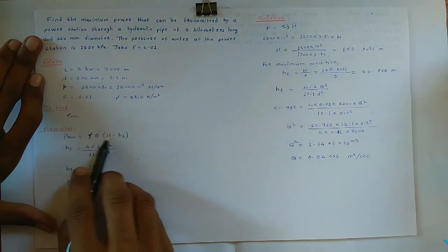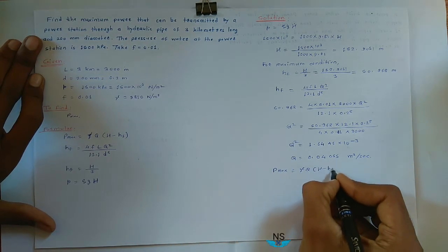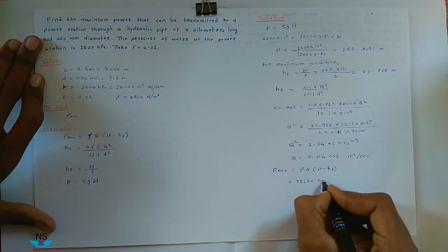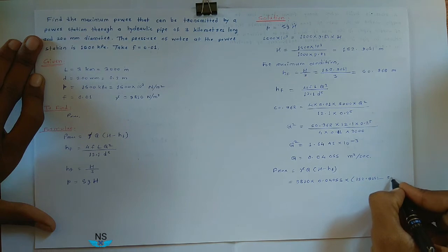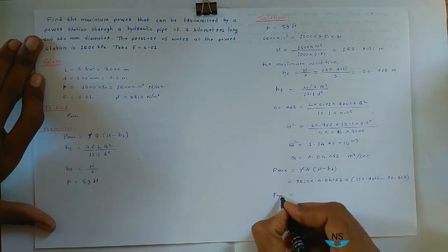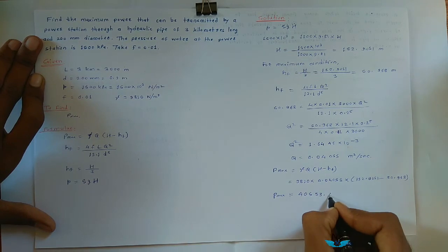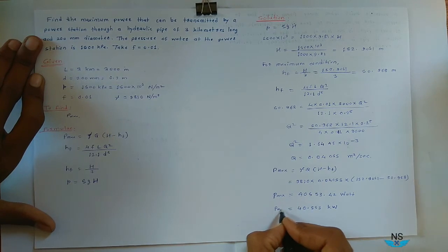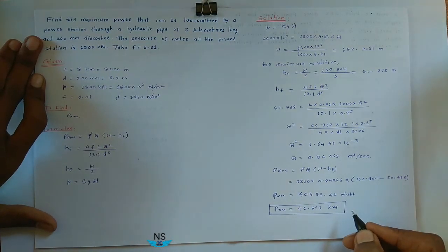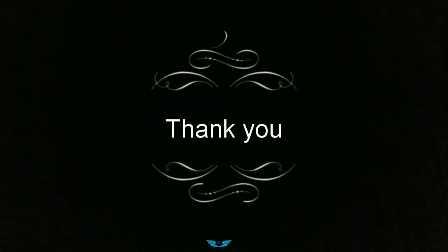So now we have all the values: gamma we know, Q we know, H is known, HF is known. So find maximum power. Maximum power Pmax is equal to gamma Q H minus HF, so gamma is 9810 into Q, 0.04055, into H, 152.9051 minus HF, 50.968. Now Pmax is equal to, put all these values in calculator, you get 40553.42 watt, that is equal to 40.553 kilowatt. This is our requirement, maximum power 40.553 kilowatt.